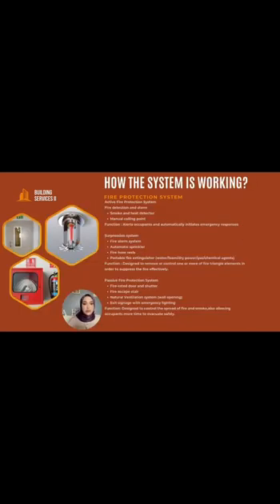Now I will explain how the systems work to maintain the building's internal environment. The first one is the fire protection system. Active fire protection systems include fire detection and alarm, such as smoke detectors and heat detectors, and also manual call points, which continuously monitor environmental conditions and transmit the signal to the FACP, the fire alarm control panel. When abnormal smoke density or temperature rise is detected, the alarm system will alert the occupants and automatically initiate emergency response. Next, suppression components such as automatic sprinklers, fire hose reels, and portable fire extinguishers, available in various types including water, foam, dry powder, gas, and chemical agent, will be selected based on the class of fire involved. Those systems operate based on the principle of the fire triangle.